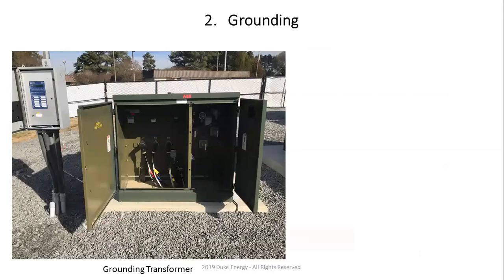But now inside the microgrid, if you have PV, battery or something like that, and you have Y grounded floating Y, which is not what you must have because of the desensitization of the settings, now you need a grounding transformer because there is no solid ground reference. A grounding transformer is a really simple transformer. This is a 500 kVA transformer that we have put in. It is Y grounded delta. You can also put in a zigzag transformer.